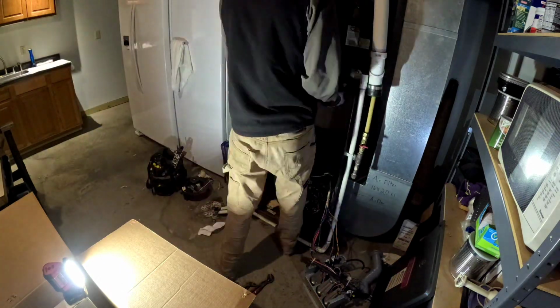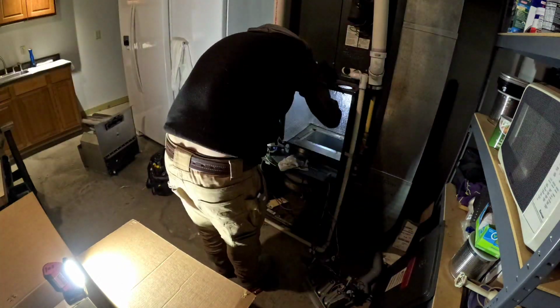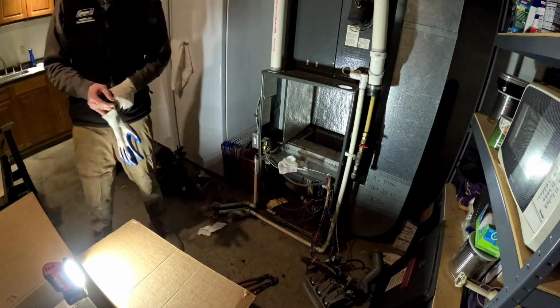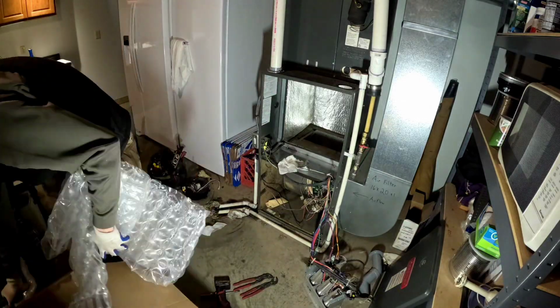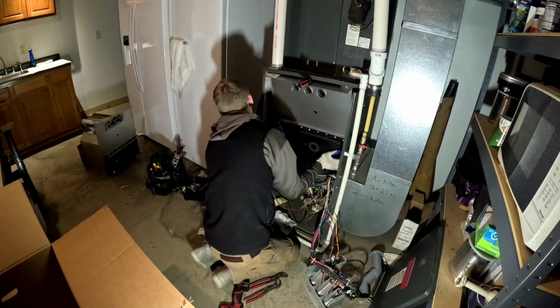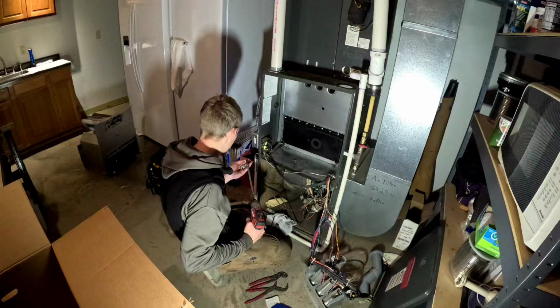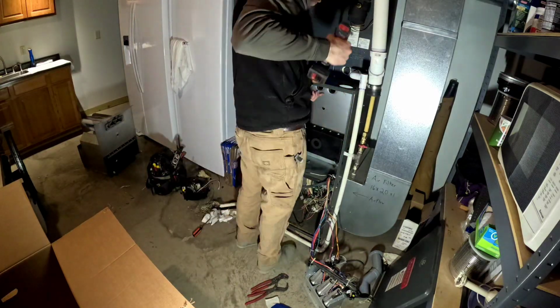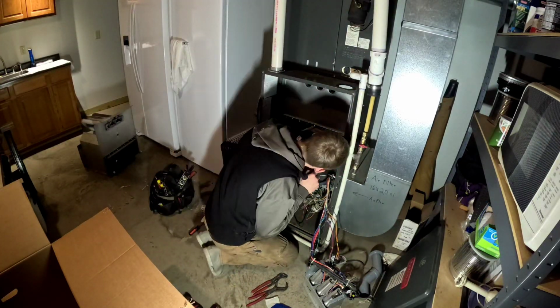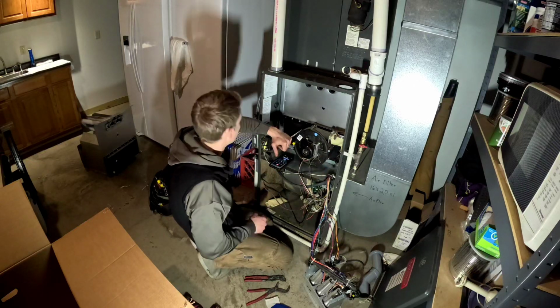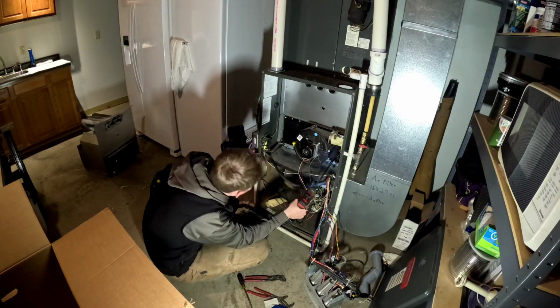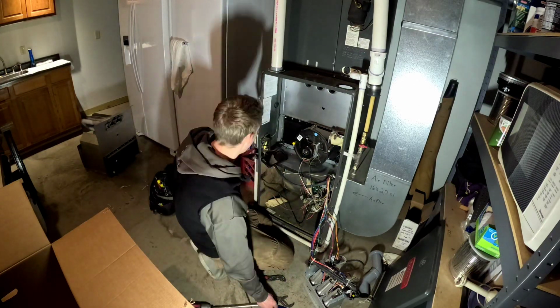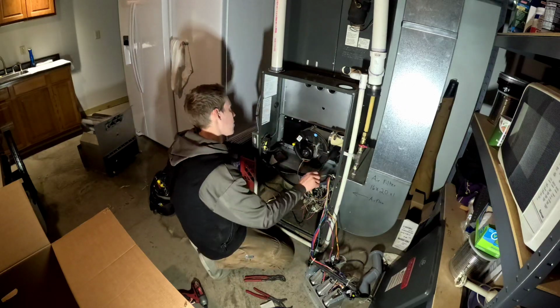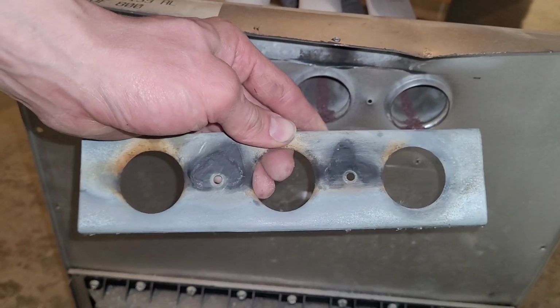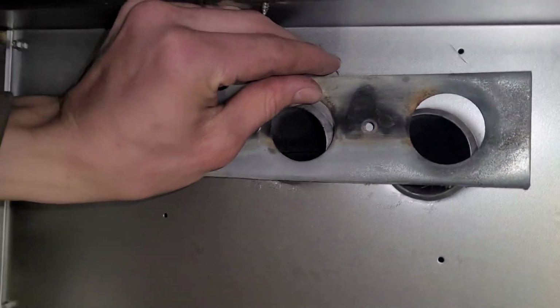For reassembly, if your unit came with some replacement gaskets, you'll just want to peel those off and stick the new ones on. This one actually did not come with new gaskets, so I just left the old gaskets in place on the heat exchanger plate. The gaskets in question are just an air seal between the plenum of the furnace and the electrical compartment. This little burner plate that's on here gets moved over to right here.